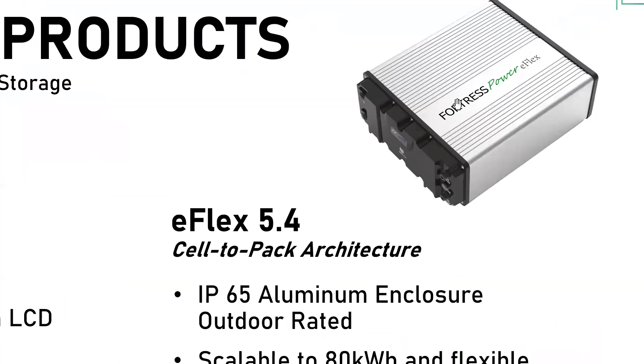Now, one thing you'll notice is this ribbing on the top of the eFlex here. This is an integrated heatsink. So this is going to have 4 to 5 times better thermal performance when dealing with colder or warmer temperatures, especially since it's outdoor rated. Our recommended temperatures are 32 degrees Fahrenheit to 113 degrees Fahrenheit. So if you expect those temperatures to get outside of that range, I always recommend different solutions, whether it be on the heating side using heat tape or a trickle charging space heater, or on the warmer side using different kinds of ventilation applications to keep our recommended temperature between 32 degrees Fahrenheit and 113 degrees Fahrenheit.